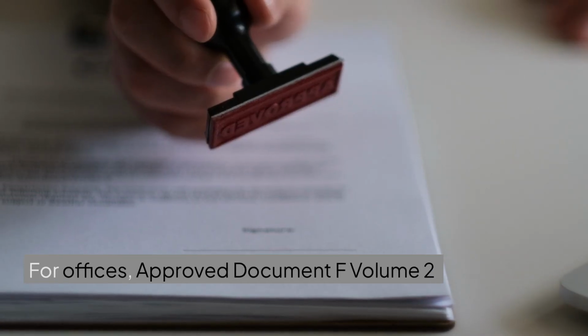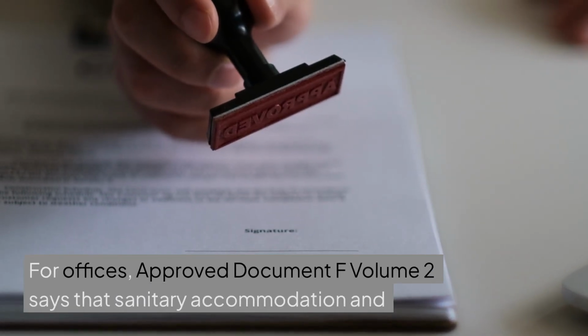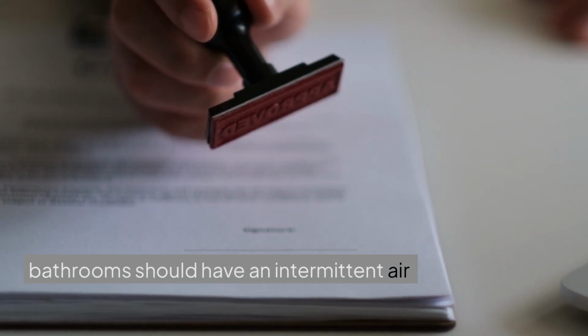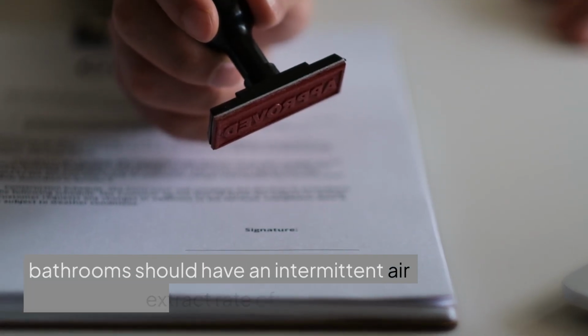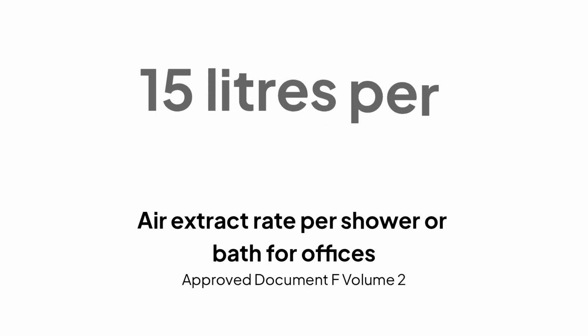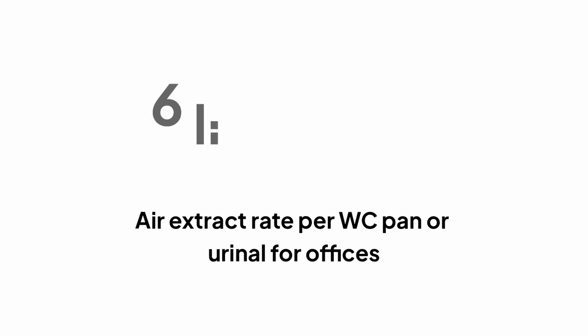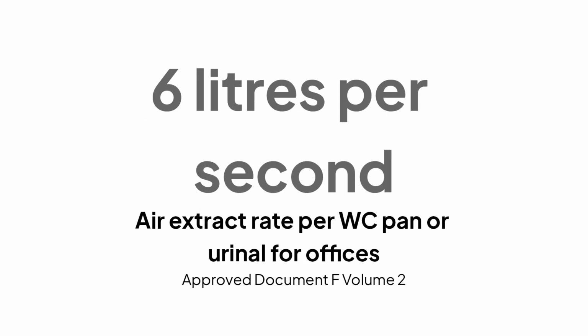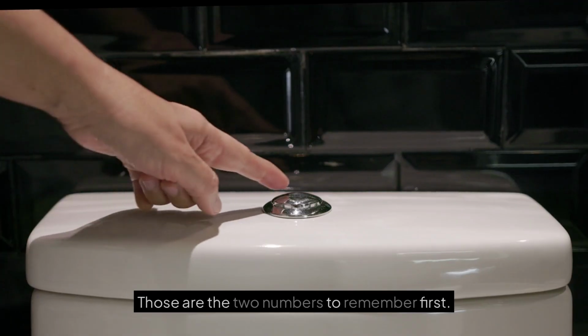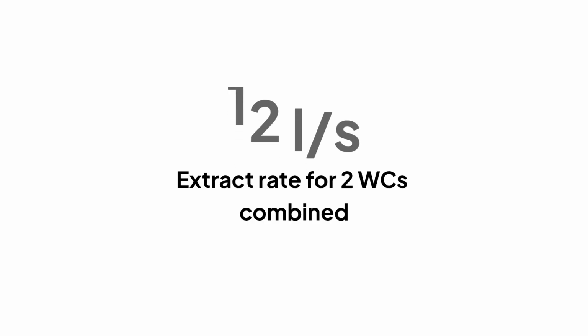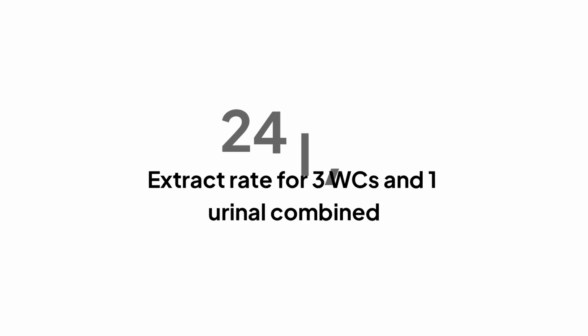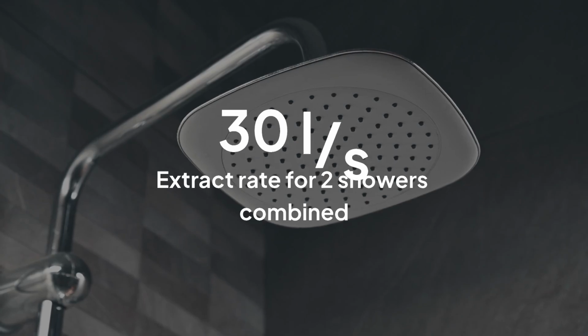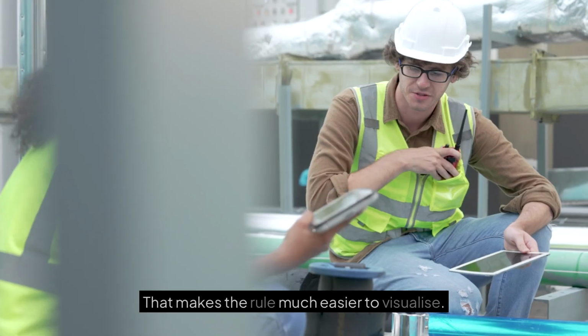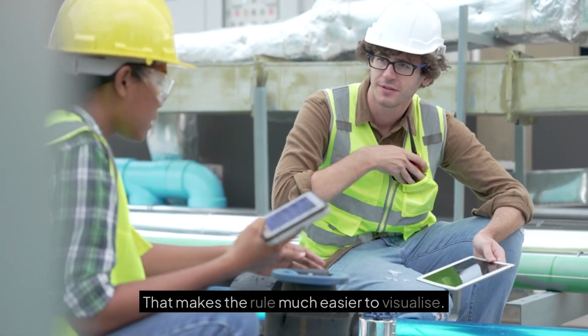For offices, Approved Document F Volume 2 says that sanitary accommodation and bathrooms should have an intermittent air extract rate of 15 litres per second per shower or bath, 6 litres per second per WC pan or urinal. Those are the two numbers to remember first. So if you have 2 WCs, that is 12 litres per second. 3 WCs and 1 urinal, that is 24 litres per second. 2 showers, that is 30 litres per second. That makes the rule much easier to visualize.